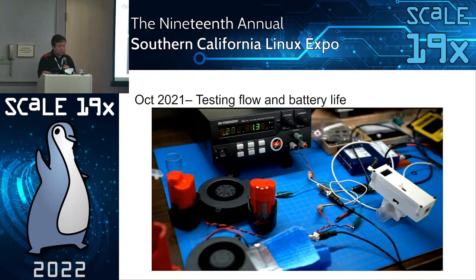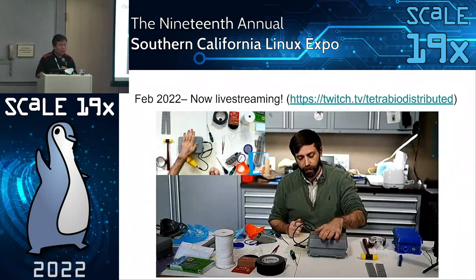One of the things we've been trying to do is use traditional blower fans, so 12-volt blower fans, because you can actually access those. They're specialty fans made for CPAP companies, and those can range over $200 a fan. We're not looking into those, because the average person is not going to be able to get that. So we're looking at devices that you can order off of DigiKey or Mouser or Amazon. So that's one of the design constraints that we have.